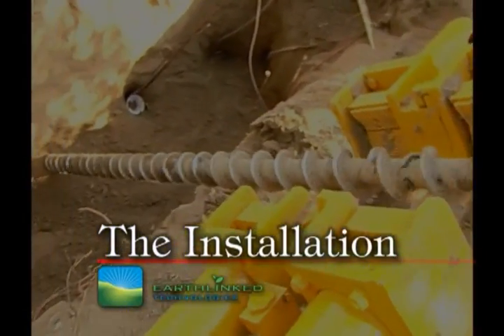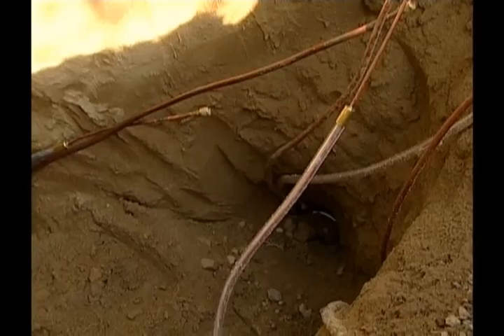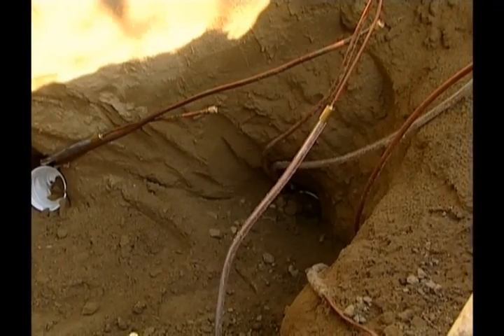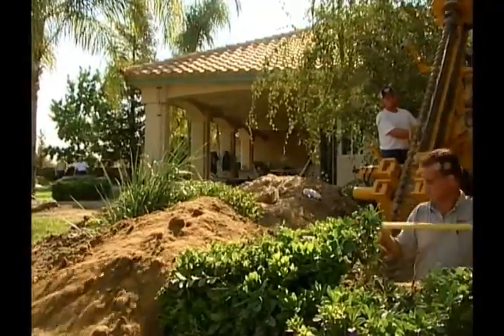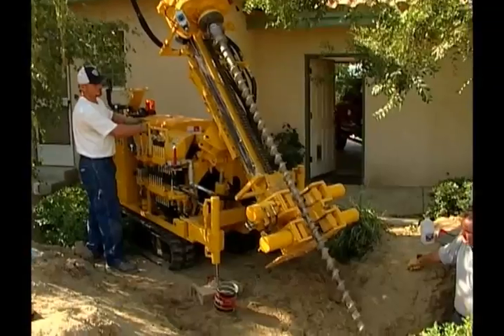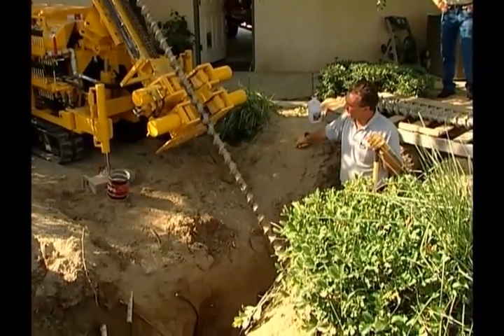Today, we're installing an earth-linked direct exchange heat exchanger. We had to come out and dig the manifold pit, which is basically the pit that we set the rig up around to drill in a fan pattern. We use what's called a DX earth loop, which consists of four 50-foot loops per ton. We have a lot of landscaping to work around, but with the rig available and the small-bore drilling, it makes it possible to retrofit almost any job.